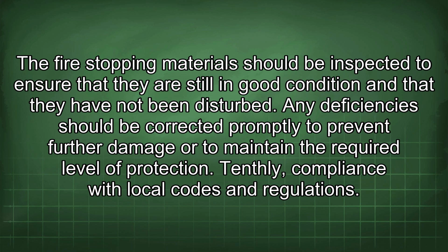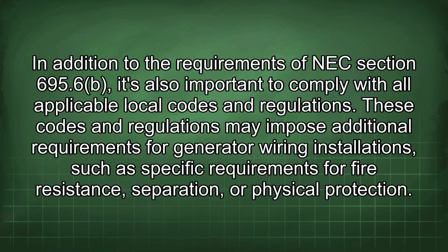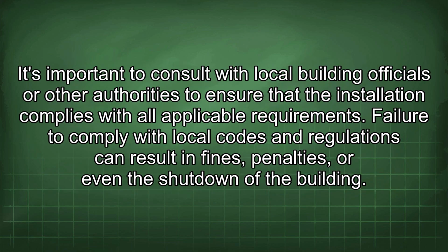Tenthly, compliance with local codes and regulations. In addition to the requirements of NEC section 695.6, it's also important to comply with all applicable local codes and regulations. These codes and regulations may impose additional requirements for generator wiring installations, such as specific requirements for fire resistance, separation, or physical protection. It's important to consult with local building officials or other authorities to ensure that the installation complies with all applicable requirements. Failure to comply with local codes and regulations can result in fines, penalties, or even the shutdown of the building.